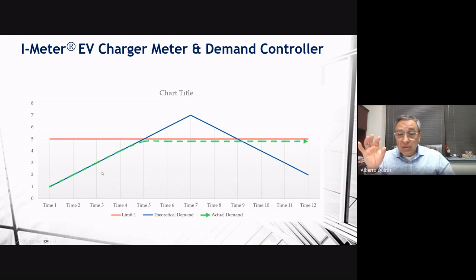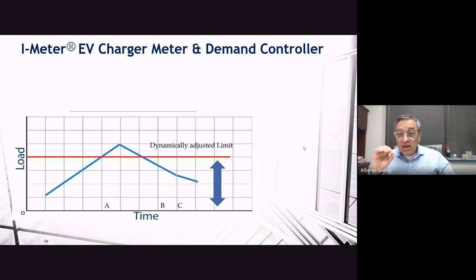for the next day. The EVCMC literally tracks the consumption of the charging mechanism and always keeps it under the limit of that capacity. The benefit is that when you add a meter to the mains of the building, that maximum capacity can be adjusted. So you can have a lower capacity for daytime when building loads are being utilized, and a higher limit at night when those loads are not used. It's very beneficial because, number one, it reduces the size of the feeder.